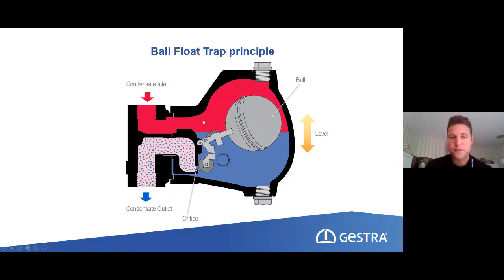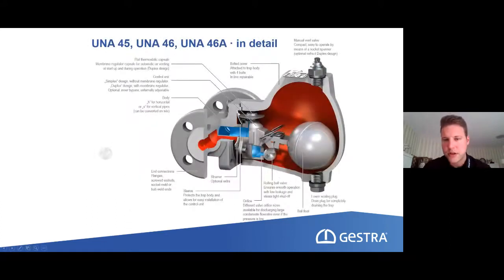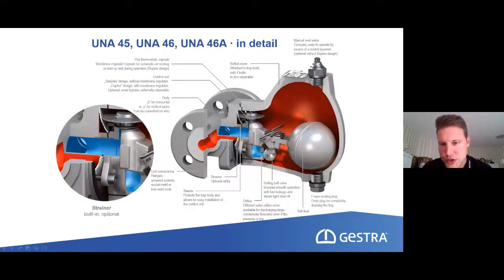But we have to get rid of it. We don't want to have it in the process. So with this design, we need something that helps us out. And we did it with this little capsule that we see here attached to the control unit inside the ball float steam trap. So this is a little membrane type capsule that we also use in our MK, so our membrane type steam trap. And this is the part that will guarantee for us, okay, we have the automatic air venting as part of the steam trap.